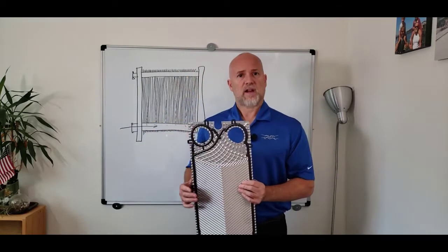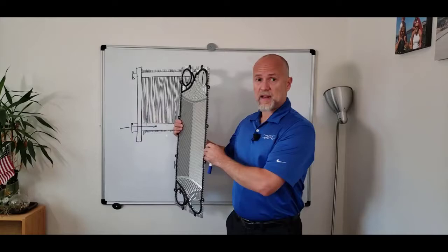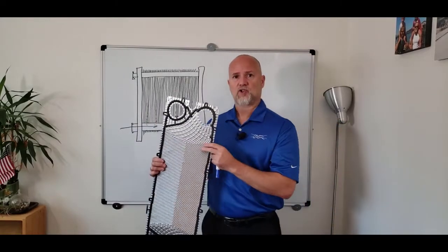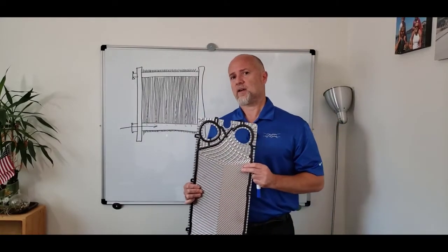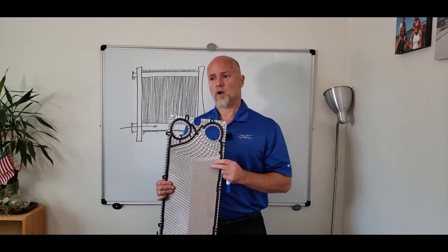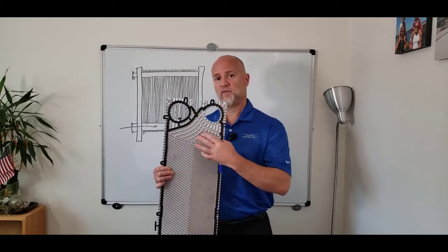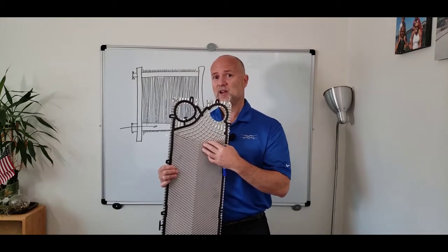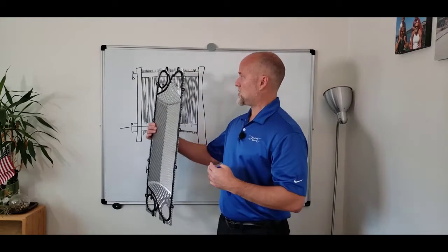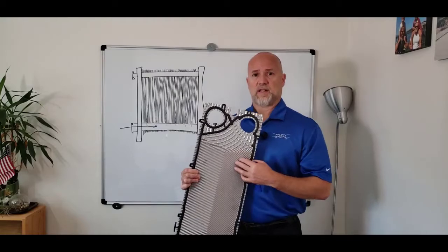And that is another reason why we say that the heat transfer area, so the amount of plates that you have in a heat exchanger, is not necessarily a good indicator anymore of comparing apple to apple, because if you have a higher efficiency plate, you need fewer plates, and so you can achieve the same duty with less heat transfer area.